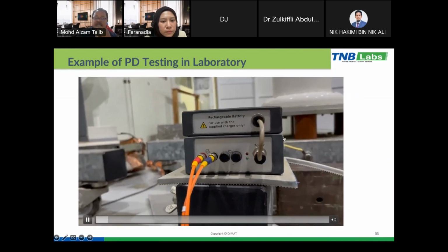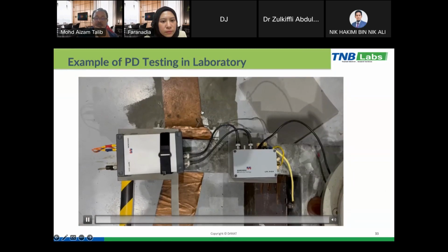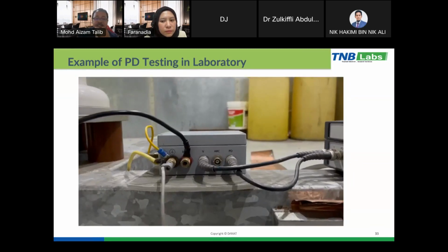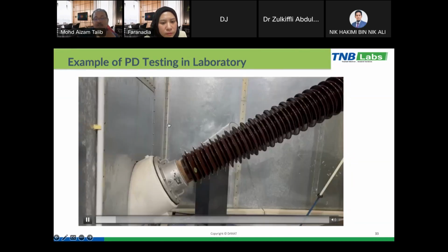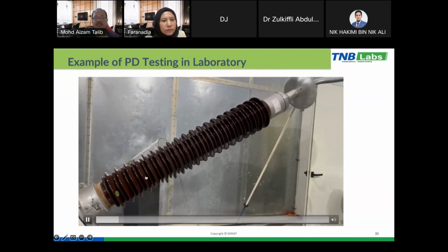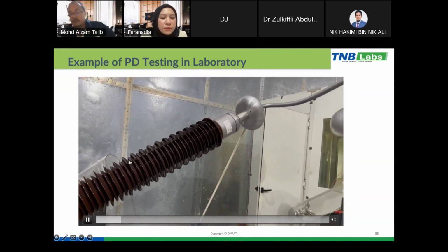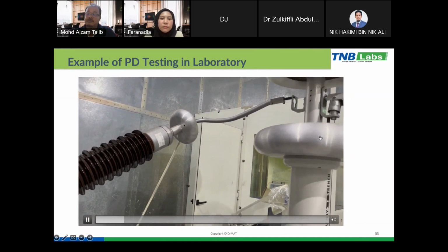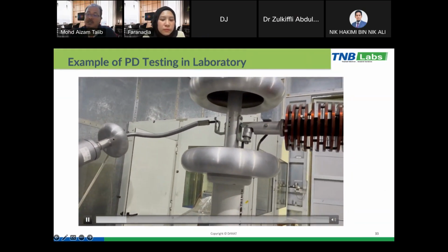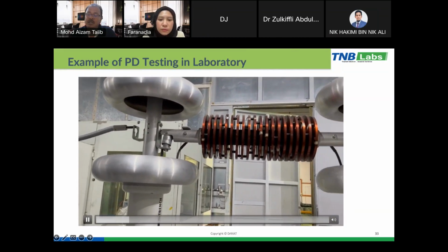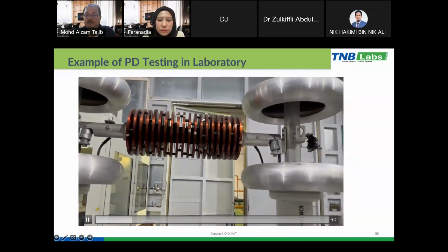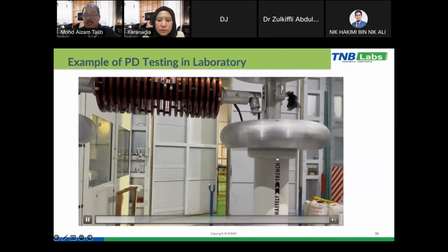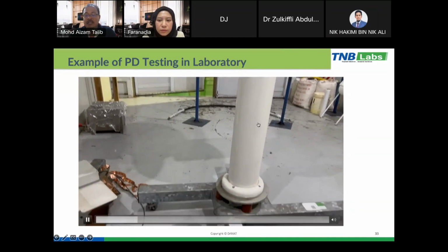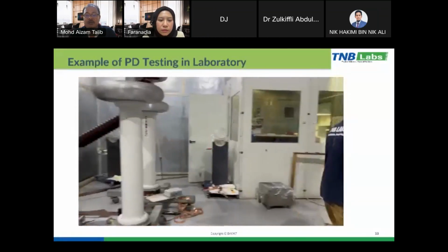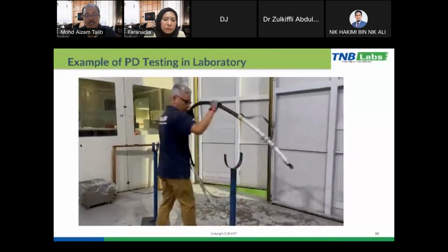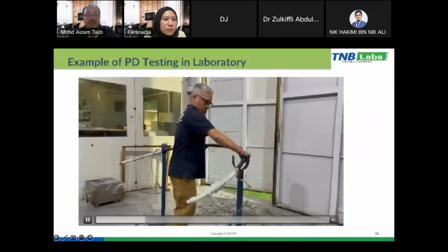Okay, this is the measuring instrument. We use the Omicron MPD. This is the matching impedance, or sometimes we call it a quadrupole. This is our HV source, and then this is the blocking impedance or HV filter. And then the white one here is a coupling capacitor, or sometimes people call it a divider. And then we have a test object. We have an 11 kV single core cable.